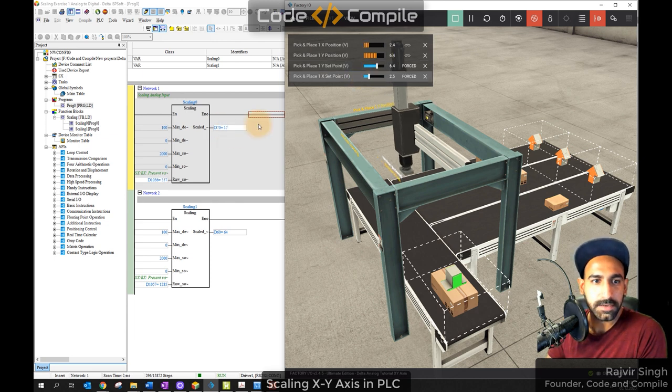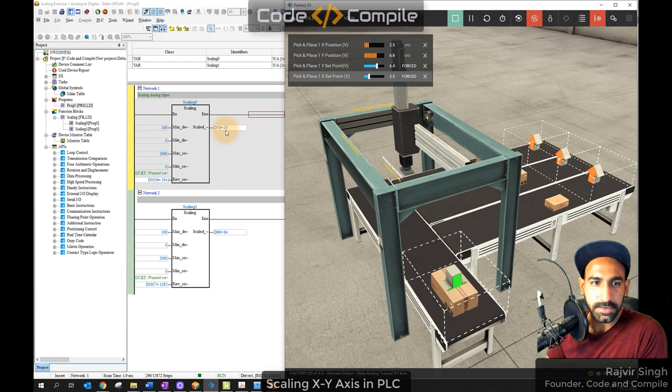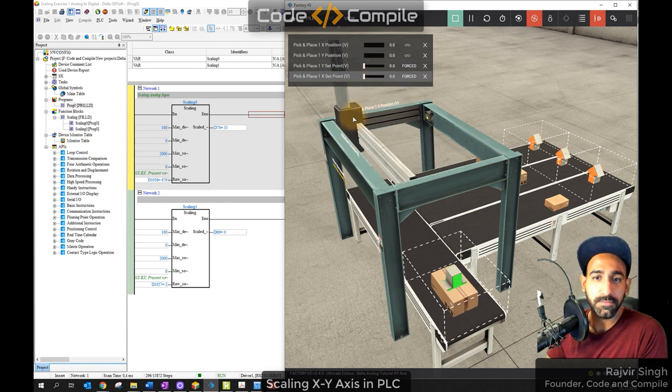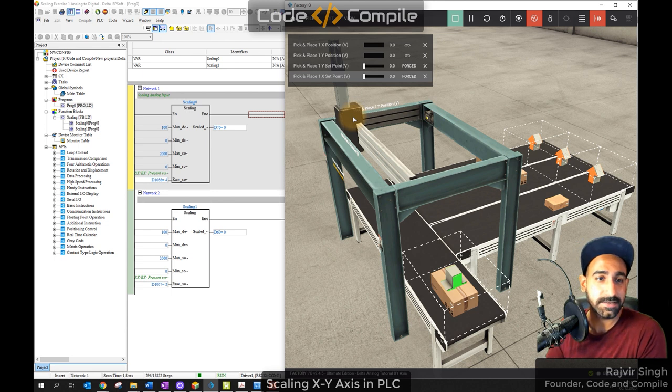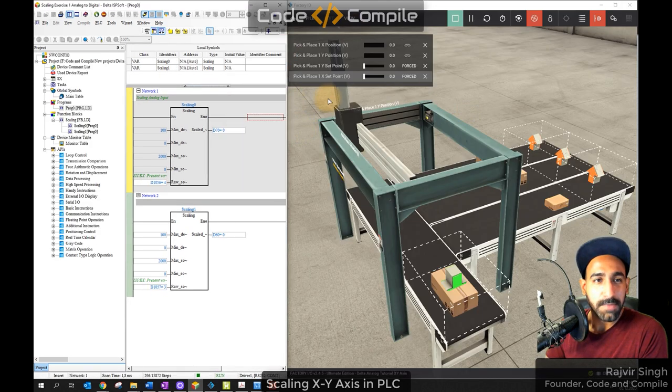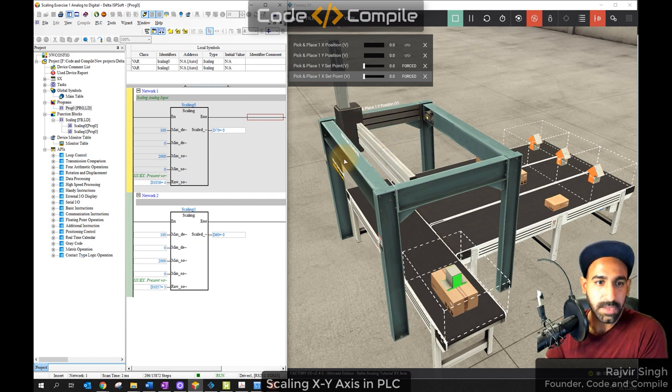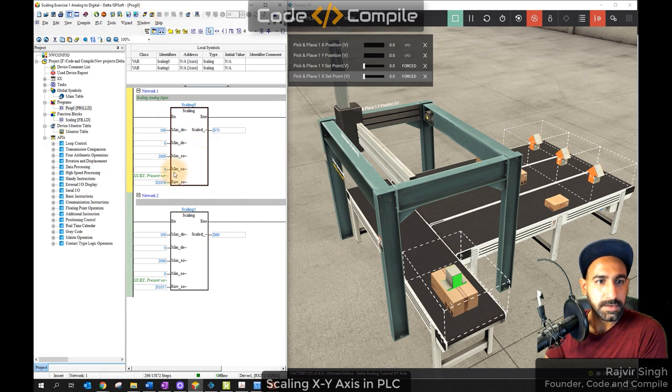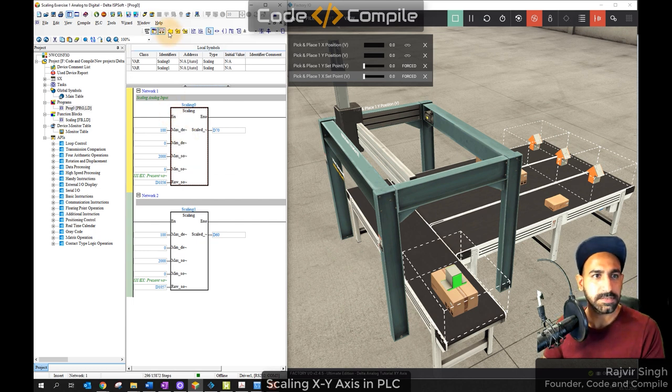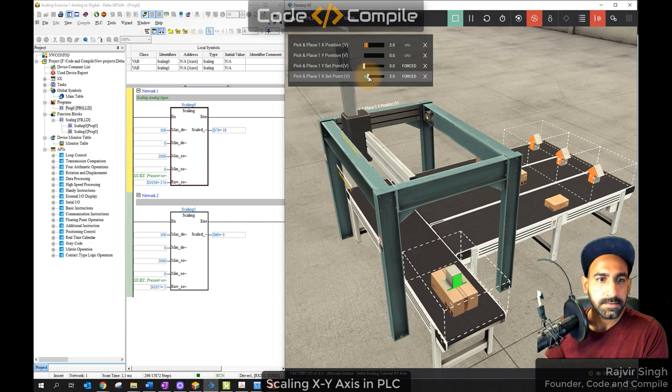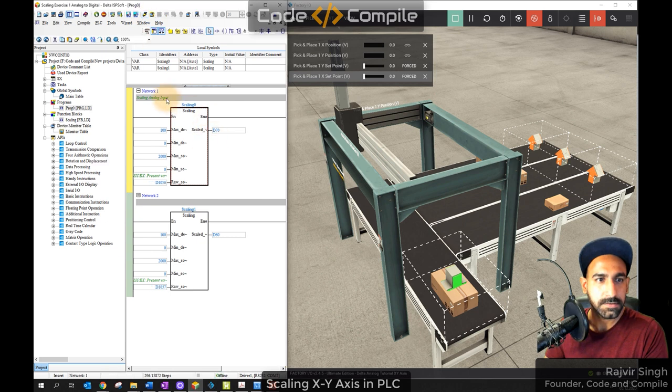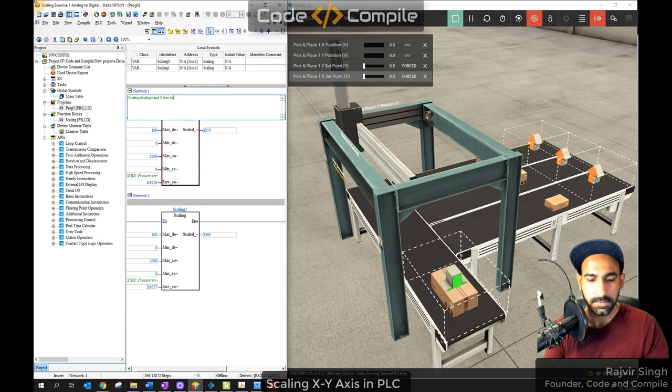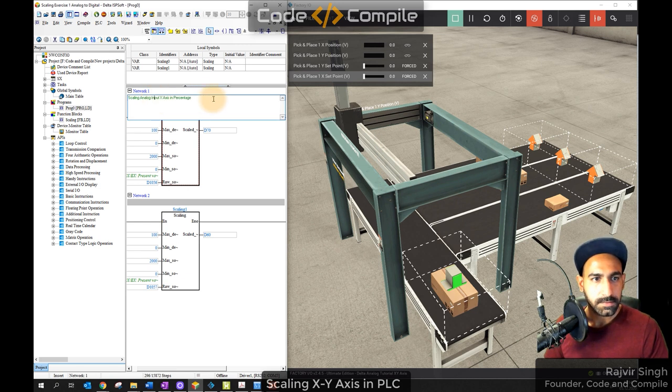Now we know that in PLC input we have 0 to 2000 decimal value. So 0 is minimum and 2000 is maximum. So you have to add constant, maximum output, maximum input. And raw value is the value which is analog input in PLC, which is analog input which is converted to decimal value. The raw value is here. And where you need the output, you add to scaled value. So this is your scale value. So this will automatically convert the value.